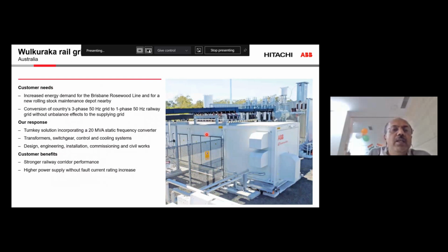There are some live cases. I will not get into much detail, but this is a very interesting application in Australia. We executed this station, which is called Wulkuraka. You can go through the internet, Google location, and here we provided a 20 MVA static frequency converter at 50 Hertz, feeding the single-phase 50 Hertz railway grid. This not only balanced the entire corridor of approximately 150 kilometer, but also compensated for the reactive power, so that the overall voltage profile is improved and the maximum demand is reduced by 20% or even more.